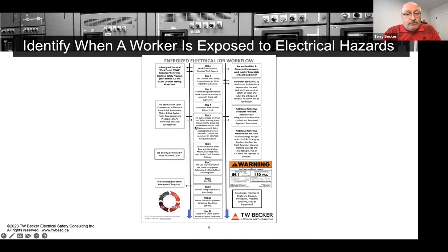So I've got this job workflow. It's a visual tool. I use it all the time because this is how we need to manage these hazards. What's the worker role? What job are they performing? Do work task hazard identification? Is there a procedure? And do they need to follow a procedure? Is there some employer field level hazard assessment document? And then 70E and Z462 kick in on the remaining steps. We need an energized electrical job safety plan, and a form should be filled out. And then the worker identifies their risk control methods they're going to apply to achieve an acceptable residual risk. And then they go into the field and apply them, establish an electrical work zone with barricading to control the work area, keep unqualified, unprotected workers out, right? And then please inspect the PPE, don it, execute the work task, doff the PPE, close out the work order.